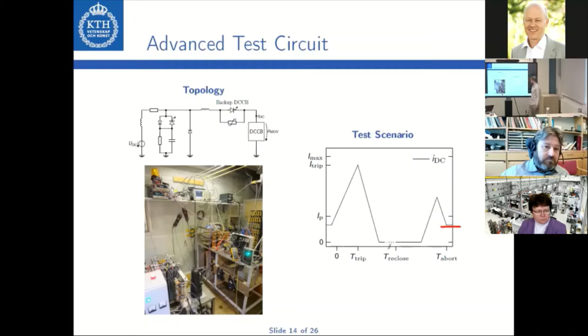The topology of the test circuit allows us to implement various test scenarios. Here you can see an exemplary test scenario on the right-hand side, where the fault current first increases in the test up to the trip level. At this point, the DC circuit breaker interrupts and the fault test current reduces to 0. After some time, the DC circuit breaker recloses. The test current starts to increase again, but it does not increase to the trip level. Because of this, the DC circuit breaker does not need to interrupt, and instead the test current reduces to the normal operation level again. This allows us to evaluate whether the DC circuit breaker can abort the proactive commutation operation after a previous interruption attempt.